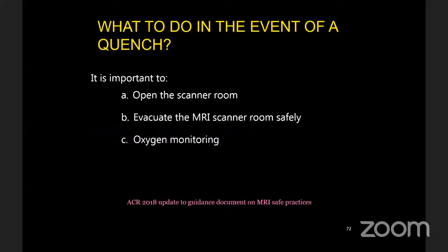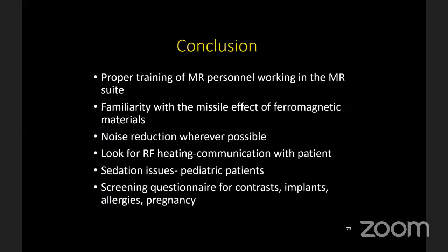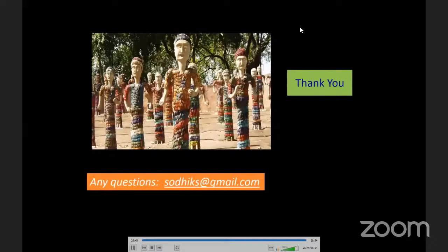In the event of a quench, open the scanner room, evacuate safely, and monitor oxygen levels if required. To conclude: proper training of MR personnel is very important and should be continually emphasized. Staff should be familiar with the missile effect of ferromagnetic materials. Reduce acoustic noise whenever possible, especially in neonates using earplugs. Look for radiofrequency heating. Communicate well with the patient. Try to minimize sedation issues with pediatric patients, and develop or use a good screening questionnaire for contrast, implants, allergies, and pregnancy. Thank you.